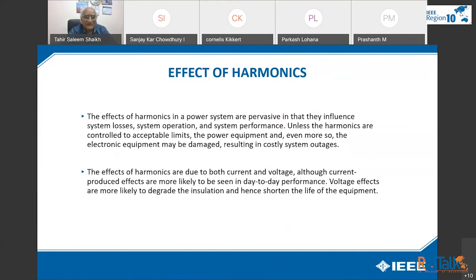The effects of harmonics in a power system are pervasive in that they influence system losses, system operation, and system performance. Unless the harmonics are controlled to acceptable limits, as described by the IEEE and IEC standards, the power equipment, and even more so the electronic equipment, may be damaged, resulting in costly system outage. The effects of harmonics are due to both current and voltage, although current-produced effects are more likely to be seen in day-to-day performance. Voltage effects are more likely to degrade the insulation and shorten the life of the equipment.